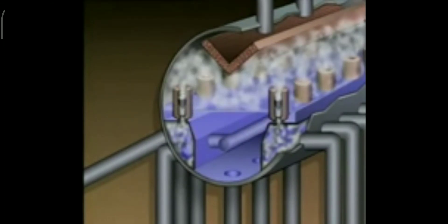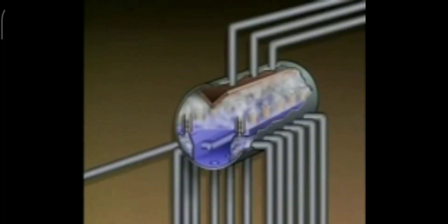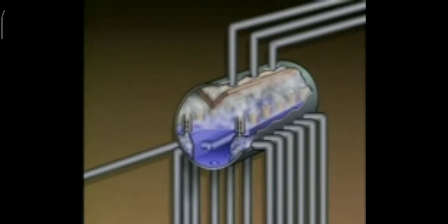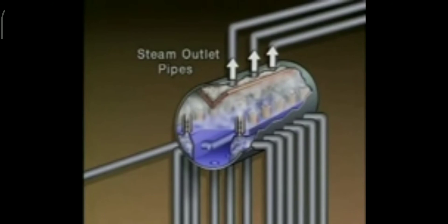The steam rises into the upper part of the drum. The steam could still have some water mixed in with it, so it is sent through dryers, which are located in the top of the drum. The dryers remove as much water as possible before the steam leaves the drum. This is important because water that flows out of the drum with the steam could damage downstream components. The steam is discharged from the drum through steam outlet pipes.